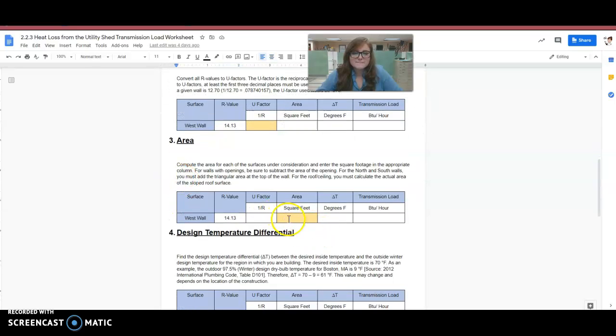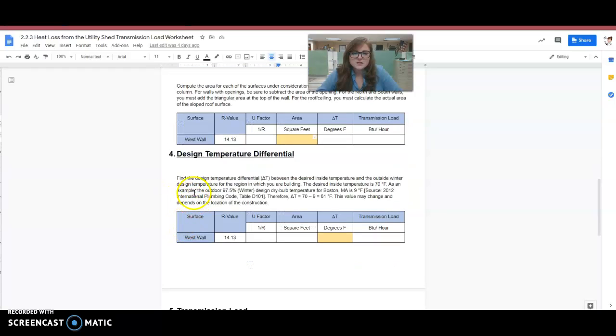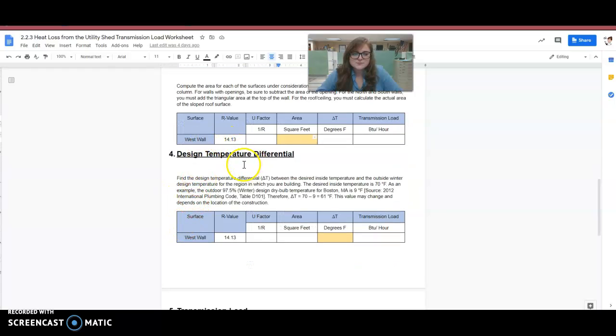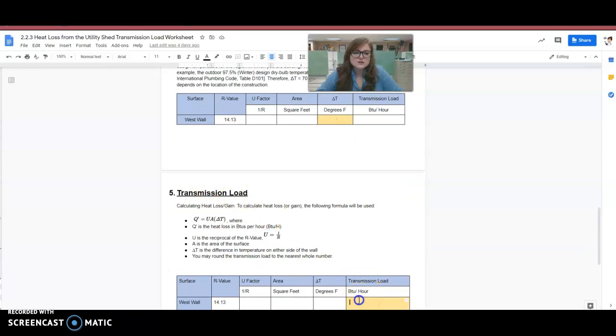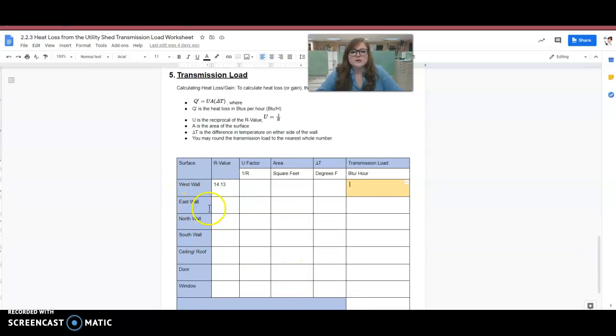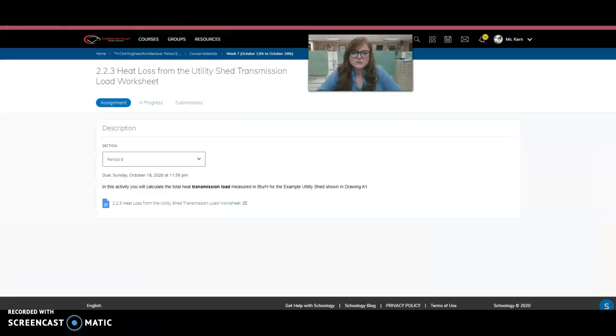Then you've got to calculate the area, put that there. Then design temperature differential, you would put that there. Transmission load here. So then you would start over again, do it for east wall, do it for north wall, do it for south wall, everything. And then finally you would get me the total transmission load at the bottom.